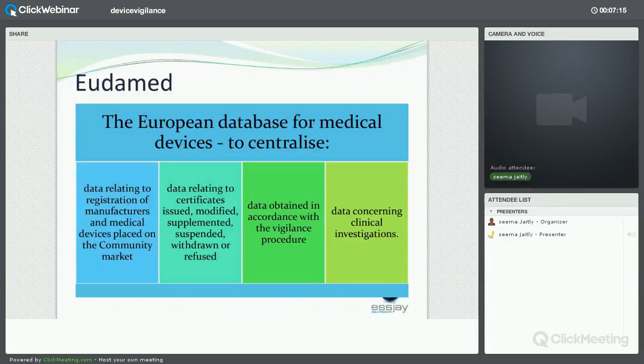So moving on to the vigilance guidelines. Here we have a guideline that's been revised in January 2013, and it talks about the medical device vigilance system. Basically, it's meant to facilitate early detection and a harmonized approach across the member states, so that you're not getting a country-by-country management of an incident or an issue that's ongoing. It's meant to harmonize and ensure that you do inform the national competent authorities appropriately of issues that are arising. And it covers incidents, which we're going to talk about, and also field safety corrective action.